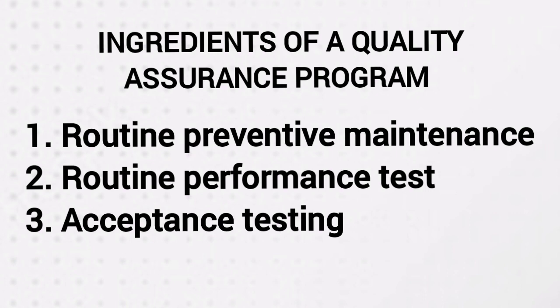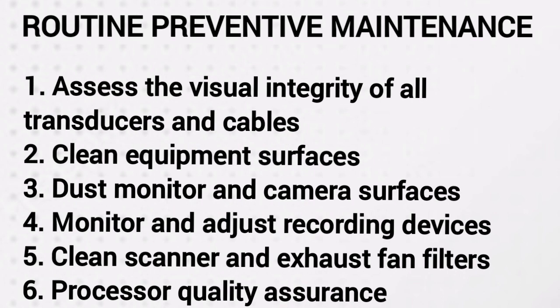I can tell you that there are three basic components of a good quality assurance program. The first is routine preventive maintenance. The second is routine performance testing, and the third is acceptance testing. Routine preventive maintenance consists of tasks that can be performed by a sonologist or a sonographer on an ongoing basis to minimize the opportunity for equipment malfunction. This includes assessing the visual integrity of all transducers and cables, cleaning equipment surfaces, dusting monitor and camera surfaces if accessible, monitoring and adjusting recording devices, cleaning scanner exhaust fan filters, and processor quality assurance where possible.